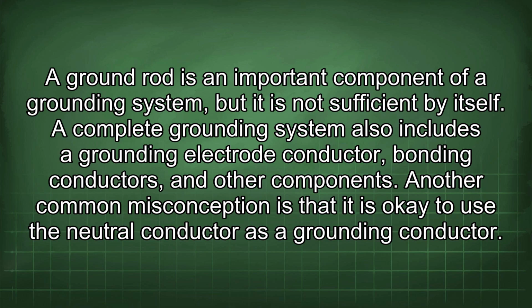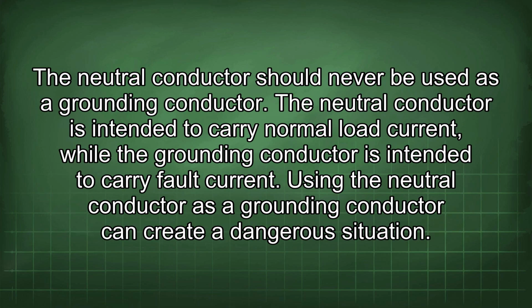Another common misconception is that it is okay to use the neutral conductor as a grounding conductor. The neutral conductor should never be used as a grounding conductor. The neutral conductor is intended to carry normal load current, while the grounding conductor is intended to carry fault current. Using the neutral conductor as a grounding conductor can create a dangerous situation.